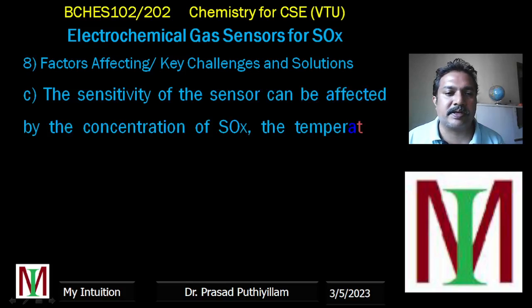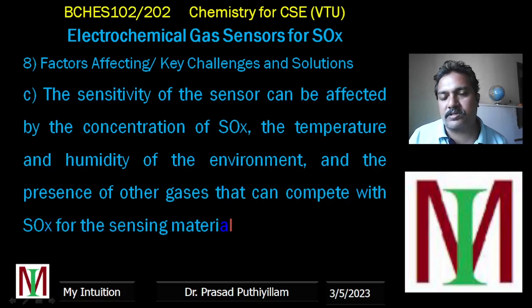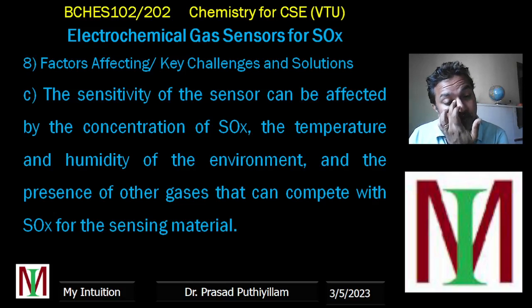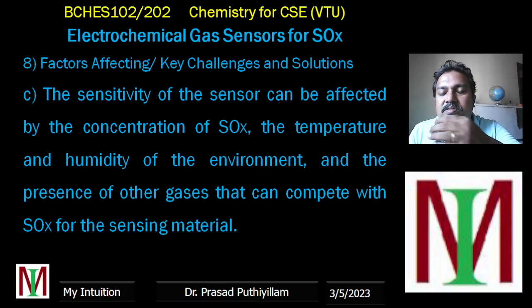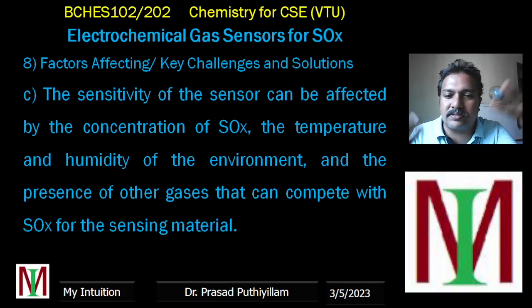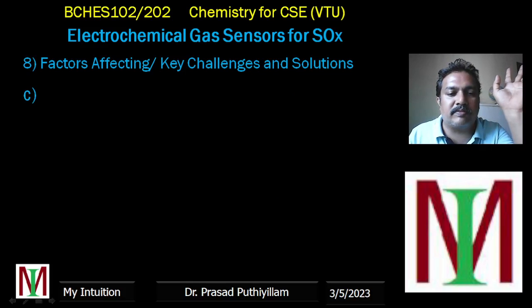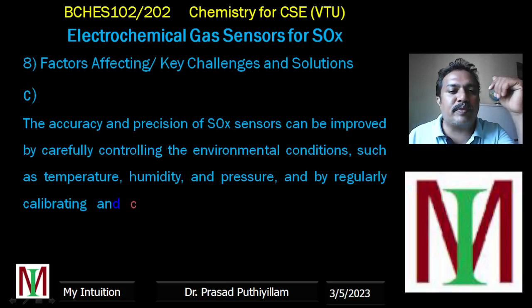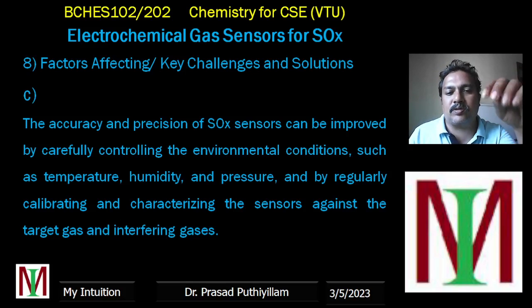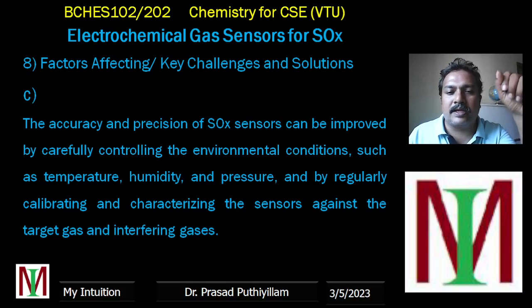The sensitivity of the sensor can be affected by the concentration of SOX, the temperature and humidity of the environment, and the presence of other gases that compete with SOX for the sensing surface — meaning other gases like oxygen or carbon dioxide may reach the sensing material first, preventing an accurate reading. The accuracy and precision of the sensor can be improved by carefully monitoring environmental conditions such as temperature, humidity, and pressure, and by regularly calibrating and characterizing the sensors against both the target gas and interfering gases.